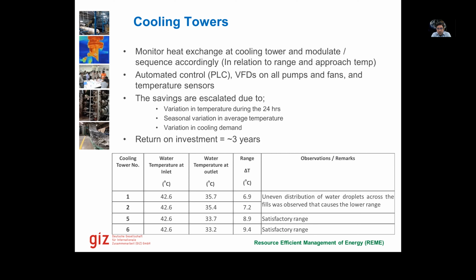At the bottom, I show you the range values that we measured in 4 cooling towers. You can see cooling towers 1 and 2 were not providing enough cooling. The delta T there was only around 7 degrees Celsius. Cooling towers number 5 and 6 were around 9 degrees Celsius. Ideally, they should be around 10 degrees Celsius.